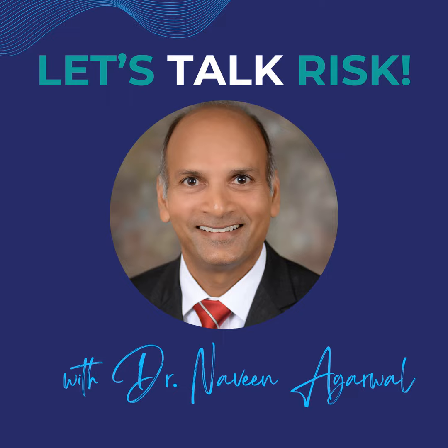An important component of this report is the human factors validation study to demonstrate effective and safe use of a medical device. A second component is a use-related risk analysis, a subset of the overall risk analysis, to identify and manage all potential risks related to the use of the medical device software.